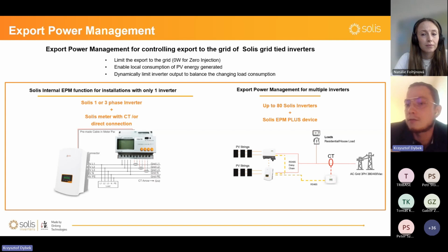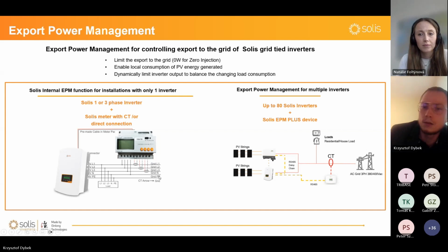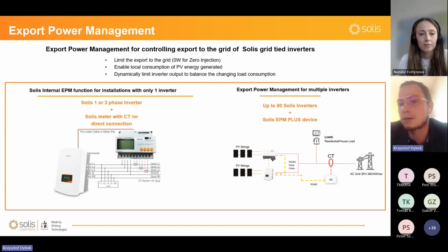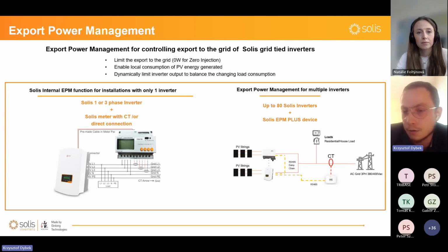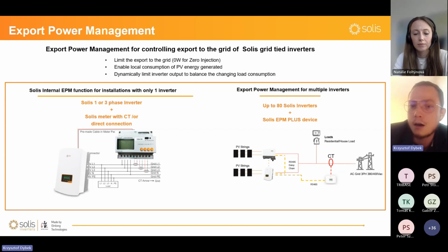So if you have only one inverter on site, like here, you can let go of this EPM because you don't need it. The inverter and the power meter connected to it will handle the job by internal EPM function. You only need to install a meter before the load. This is one scenario. Or before the load and the inverter. This is the scenario that I personally recommend, having the best results. And install CTs, current transformers, I mean, that come with the power meter together.